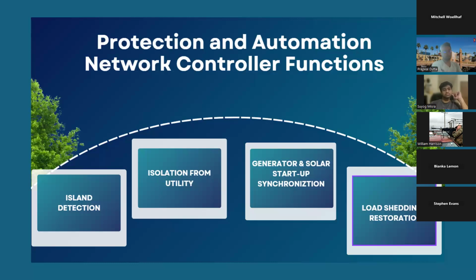Thirdly, generator and solar startup and synchronization. Once isolated, the controller initiates a smooth startup of backup generation. Synchronization logic based on phase, voltage, and frequency matching is executed to connect sources like solar and diesel gensets safely in our system. Next, load shedding. If generation can't meet demand, non-essential feeders are shed using the SEL 751 relays based on priority tags. This avoids brownouts and total collapse and maintains stability for critical loads.